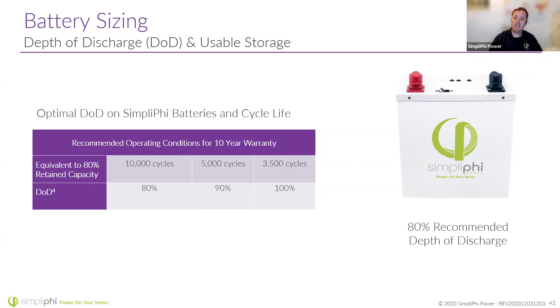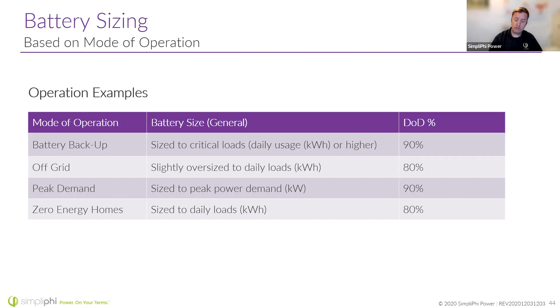But maybe you're in a situation where you're really not cycling that battery every day - a battery backup, or maybe you're just shaving peak demands. Go ahead and size for a 90% or 100% depth of discharge. You don't really need that extra capacity. You're not cycling it every day, so it's more acceptable to do a 90%, 100% depth of discharge in those situations.